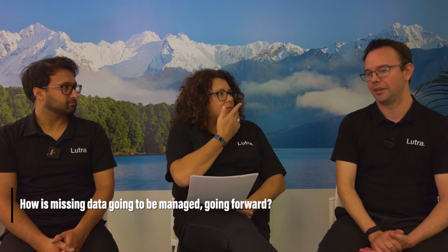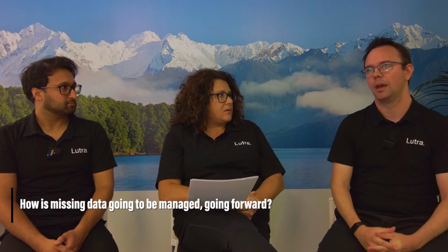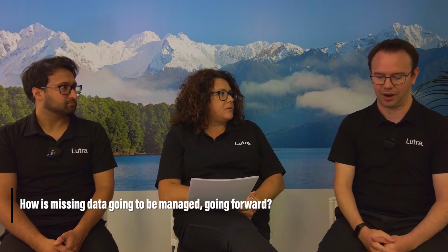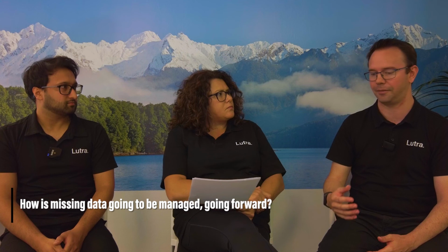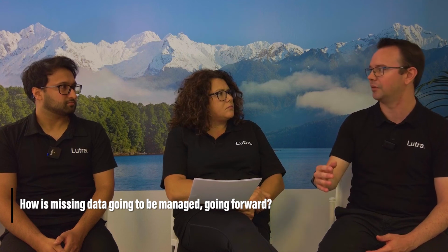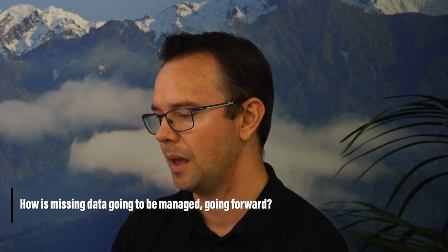And this is a really big one, and we all know about this from our experience, and it's about missing data and missing minutes. So, give us a good rundown on how this is going to look going forward. Yeah. So missing data, and what the requirements are for compliance, has been clarified. Effectively within this draft exposure, missing data will cause non-compliance if within a day you either have 15 consecutive minutes of missing data, or you have a total of 72 minutes of missing data.